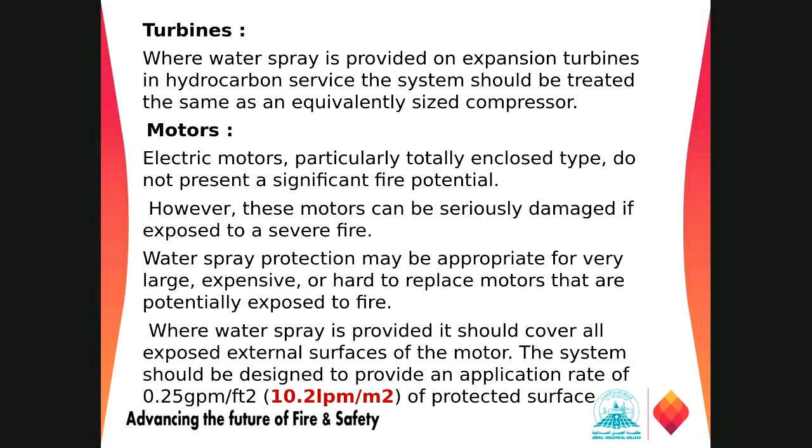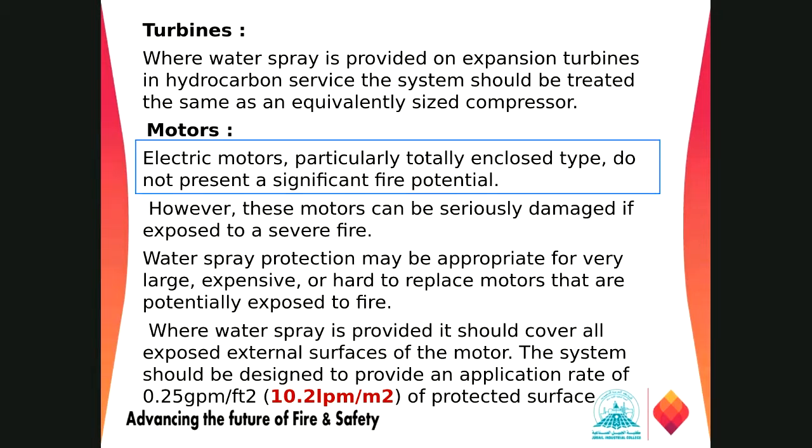Or for electrical motors, particularly totally enclosed type, they do not present a significant fire potential, right? So normally a motor which is totally enclosed means there is no connection between the outside atmosphere and the inside atmosphere. It's totally enclosed from the atmospheric condition, but it may be damaged due to exposure to a severe fire. If fire is in nearby areas, it might damage the motor. So for that, we need water spray protection.